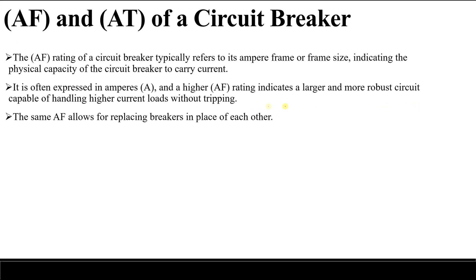There is another important point regarding AF. If we have two or several circuit breakers with the same ampere frame, it means we can replace them in place of each other. So if I have a circuit breaker installed in a certain location with an ampere frame of, say, 250, and another circuit breaker also with 250 ampere frame, we can swap them in the same location. This usually means they have the same physical dimensions.